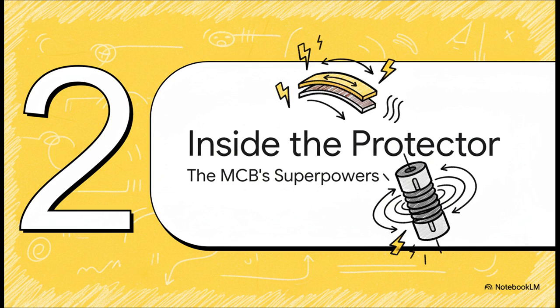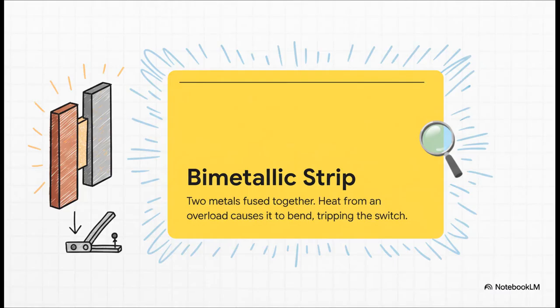So, the big question is, how does one small device protect against both a slow, creeping danger and a sudden, violent one? Well, it's because the MCB basically has two distinct superpowers, each one perfectly designed to counter one of those threats. First, let's talk about the overload watcher, a component called the bimetallic strip. This thing is so clever, it's just two different metals, say steel and copper, bonded together. Now, when an overload causes that slow, steady increase in current, this strip starts to heat up, and because those two metals expand at different rates when they get hot, the strip starts to bend. It's patient, it waits. And if that overload condition continues, it bends just far enough to physically push a lever and trip the switch. Simple, but effective.